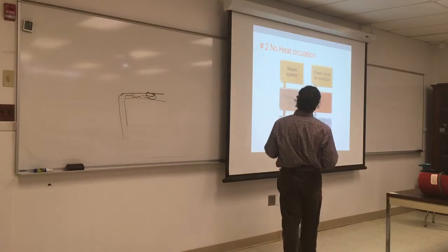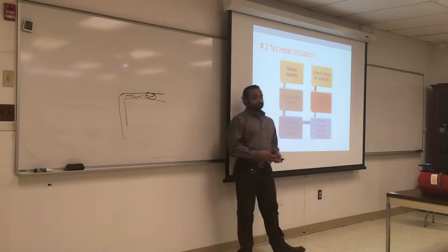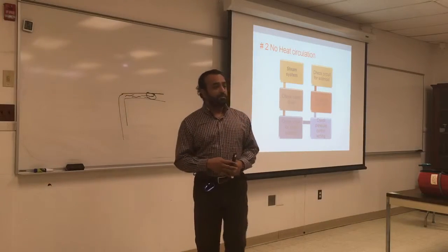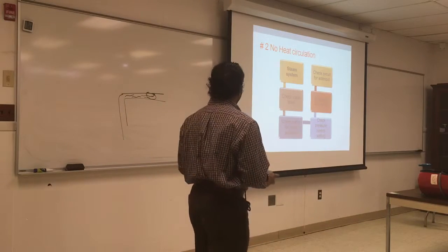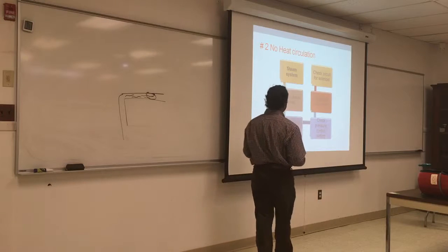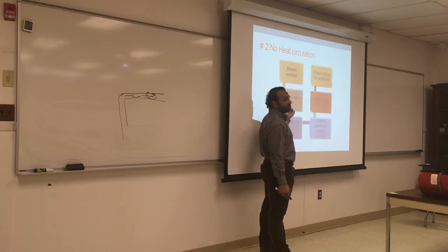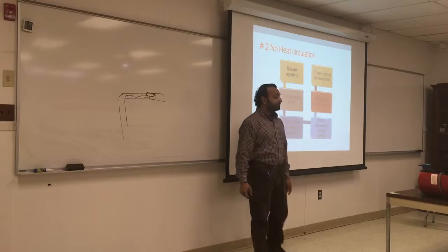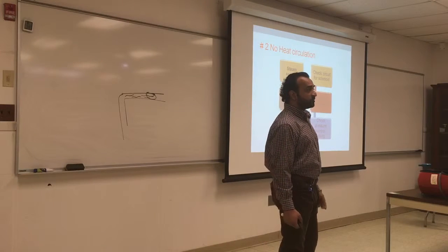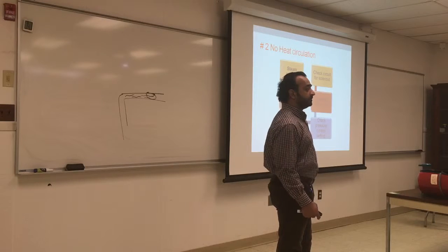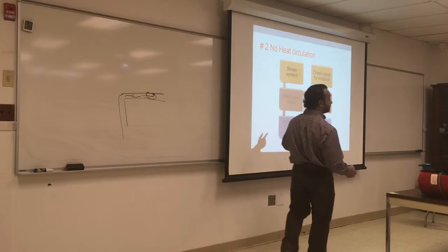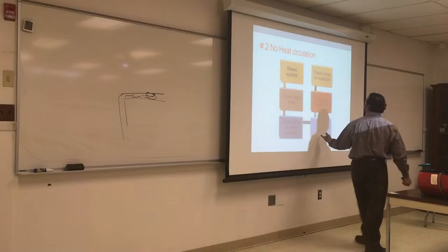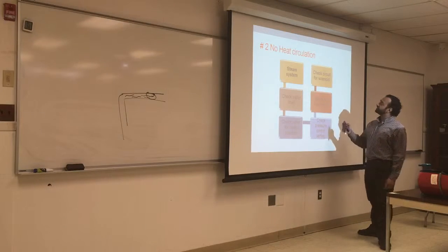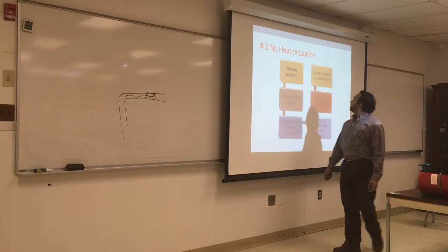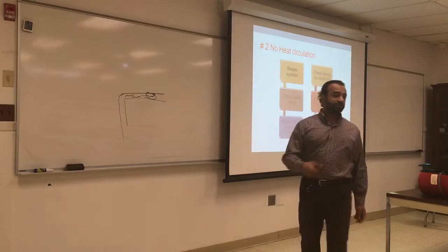No heat circulation again, for a steam system. Steam does not require a pump. The steam goes by itself. Check the water level. If you don't have enough water, you're not going to make enough steam to circulate. Check that valves are in the open position. If you have a valve on the steam line and it's closed, the steam is not going to move. Check the pressure control setting, main vents, and the circuit for the solenoid, if you have a solenoid.